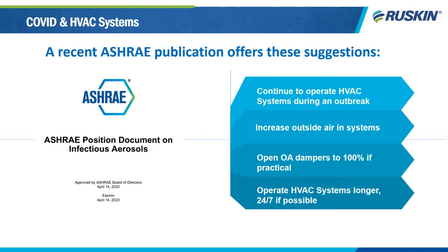One of the suggestions is to continue to operate the HVAC systems rather than shutting them down. There could be a fear of transporting the virus through buildings if you operate the HVAC, but with proper filters and ventilation, the benefits of operating the system outweigh the disadvantages and actually create a healthier building. Another suggestion is to increase the amount of outside air as much as you can, as Glenn mentioned. Open the outside air dampers as much as you can, 100% if you can at all. And another idea is to operate the HVAC systems for longer periods of time, 24/7 if possible. That should result in more outside air changes per hour within the space.